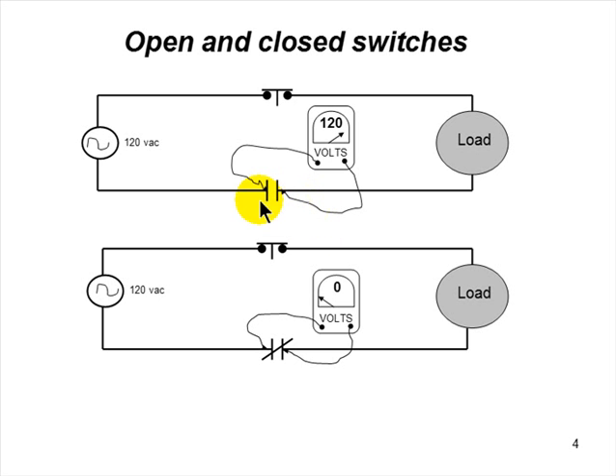Potential is the potential to do work. When you plug this meter into a receptacle in your house, and it says 120 volts, there's nothing else plugged into that receptacle. But you have the potential to do 120 volts electrical pressure of work. When you hook a motor into it and then you read across the motor, what you're reading is the voltage drop across that motor relative to the potential that created it. All right? Don't lose a whole lot of sleep about that, but I had to try to clarify that.